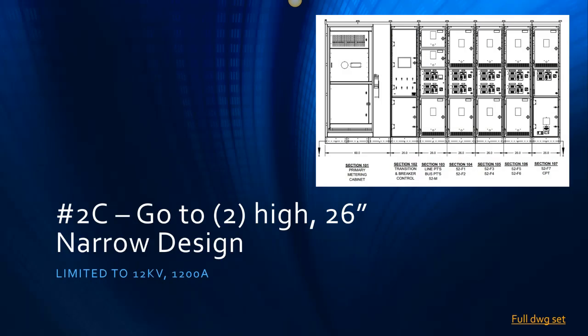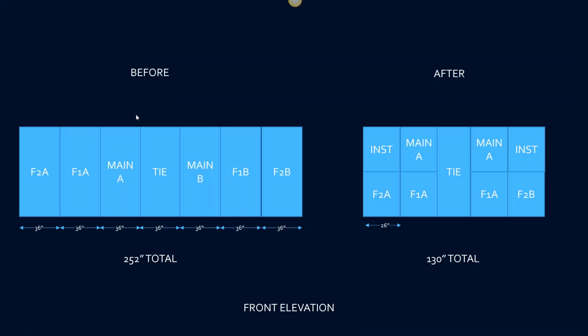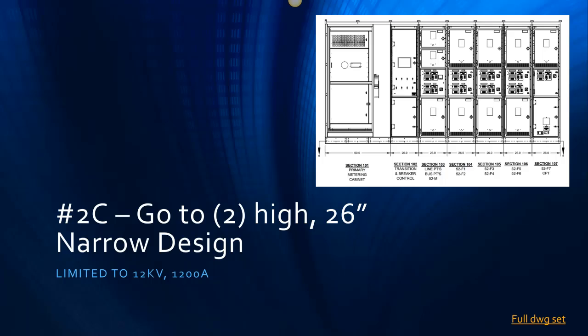This is a wonderful design as well. This is a 26-inch wide design that's two high. This is rear connected, so you're not going to be able to use the front connected in this configuration. But, and this slide is actually wrong, I apologize. This is limited to 15 kV and it's 2,000 amps. So the drawing that this came from, the manufacturer can do this up to 2,000 amps. Okay. The feeders can be 2,000 amps as well there, Michael, at 26 wide? I believe so.